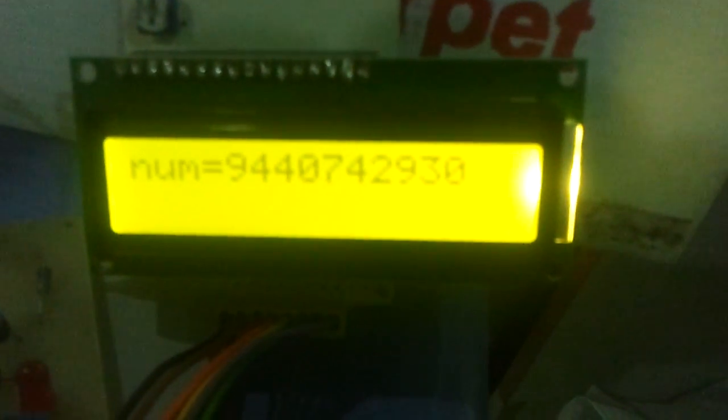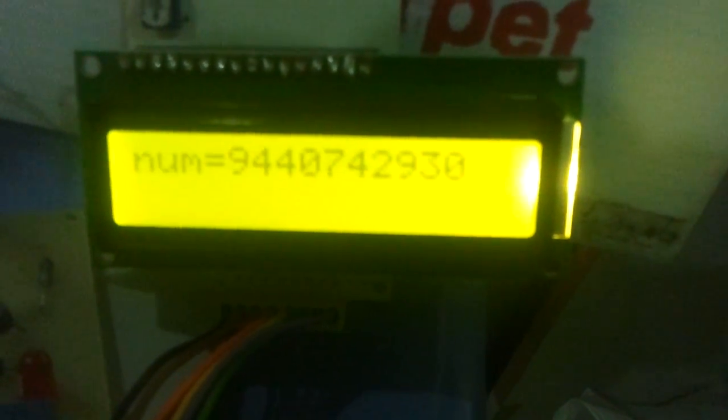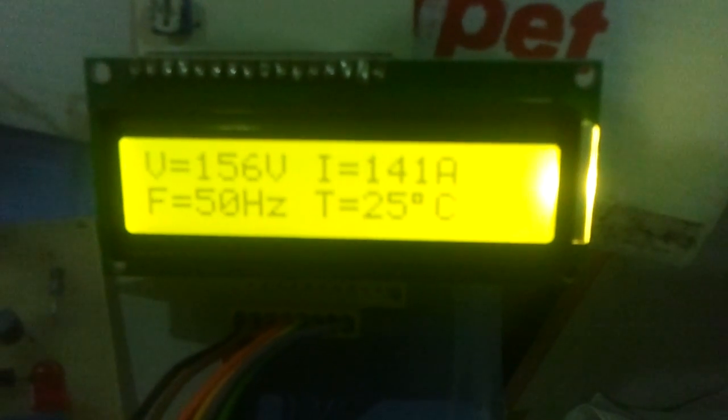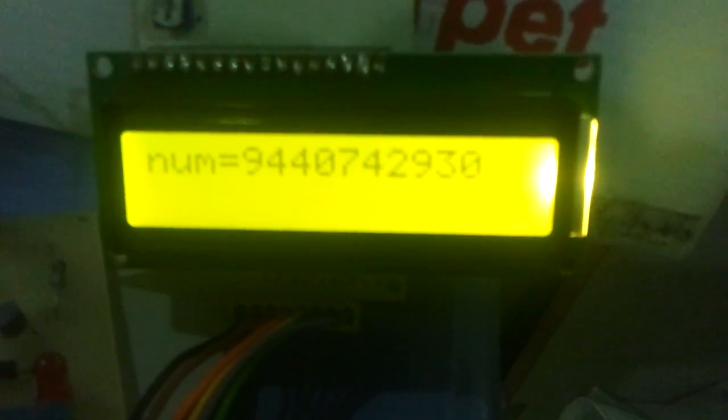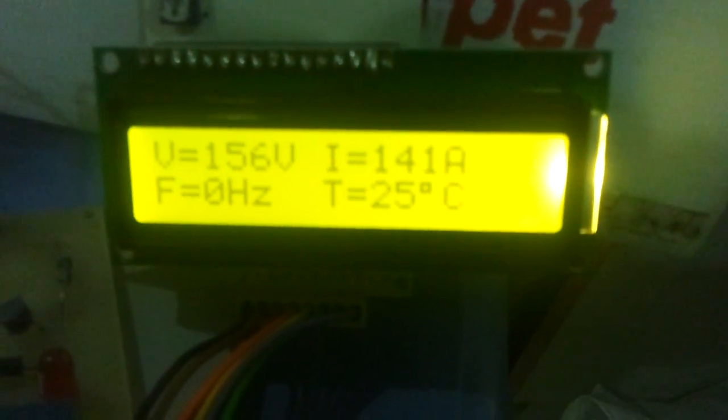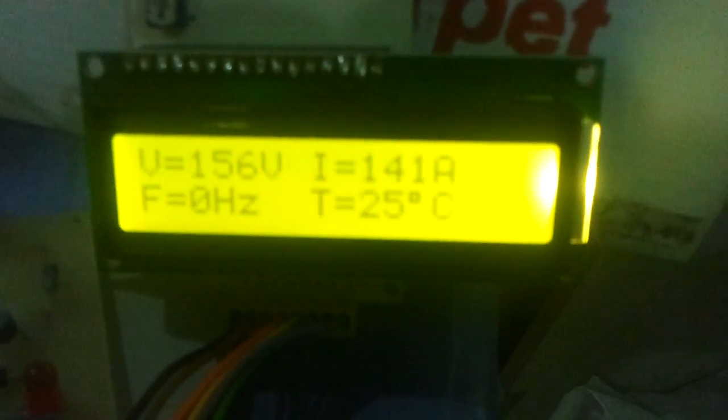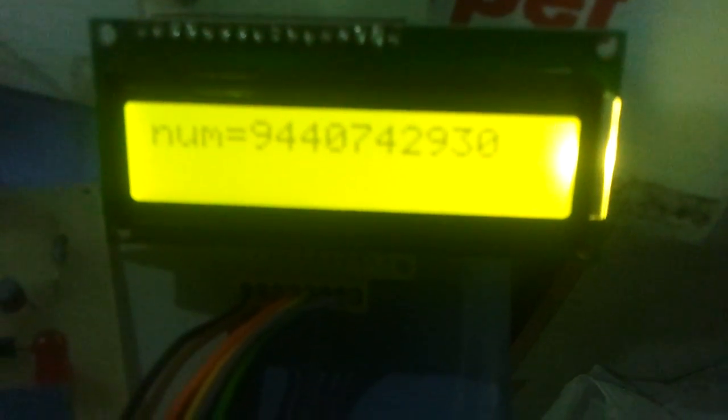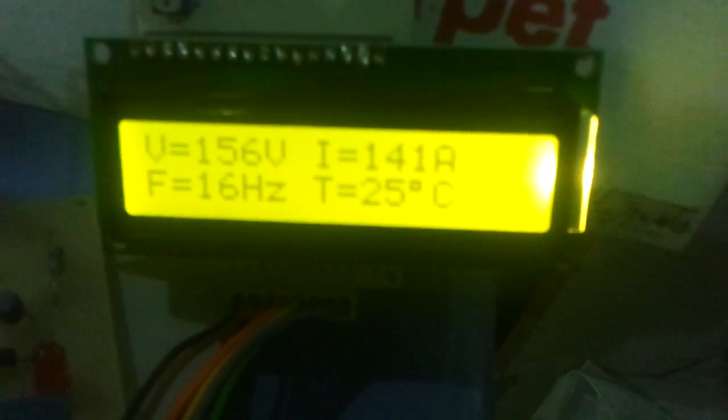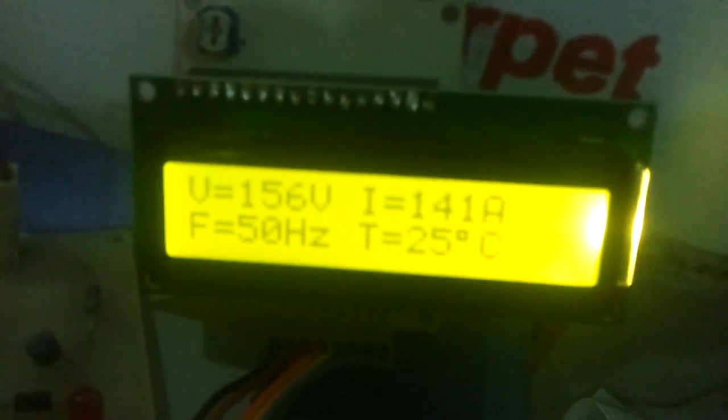See here I received the parameters - the live parameters including voltage, current, temperature and frequency. Let me turn off the frequency sensor now. The frequency should become 0. See the frequency has become 0. I am turning on the transformer. Now it calculates the frequency and the frequency measured is 50 hertz.